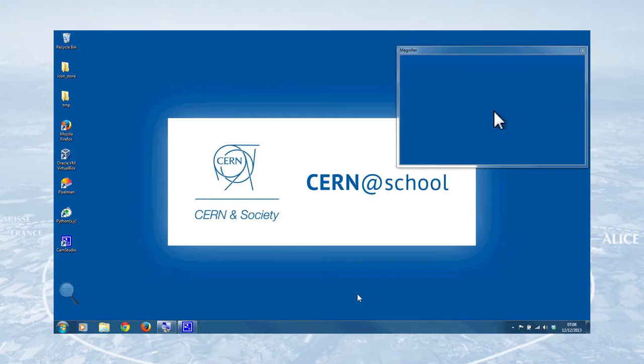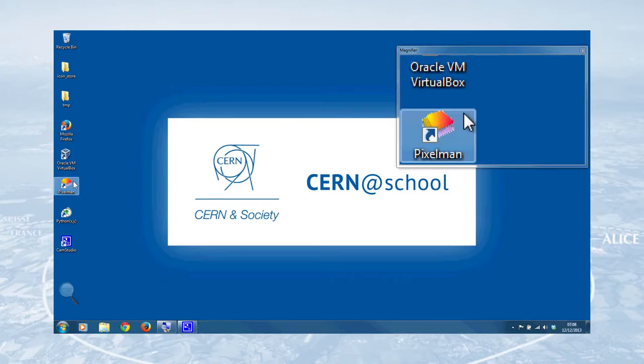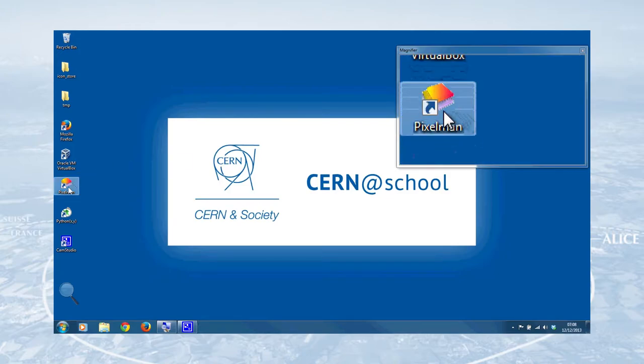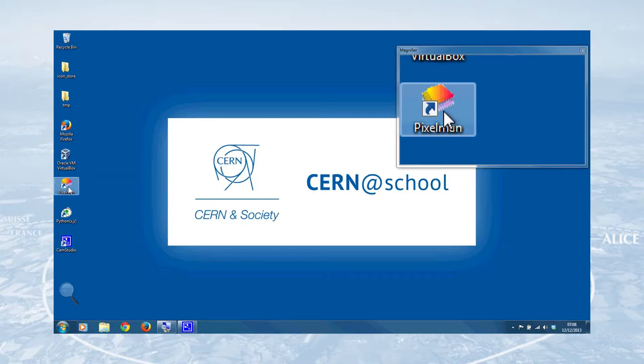Now you should have your MX-10 plugged into your laptop via the USB cable, and it should be set up ready to do the experiment that you want to do. Once you've done that, you're ready to double click on the Pixelman icon that should be on your desktop. This will start the Pixelman software running, and this is used to run the detector, look at the data that you've taken, and then save it for later analysis.